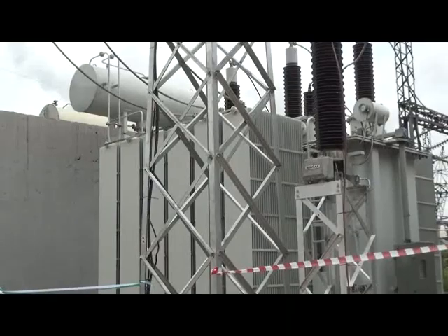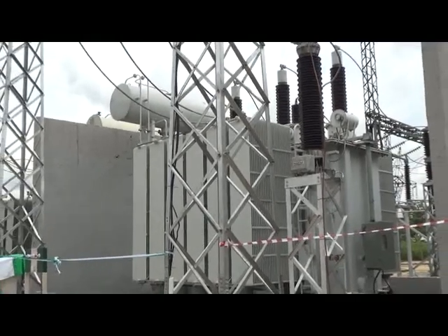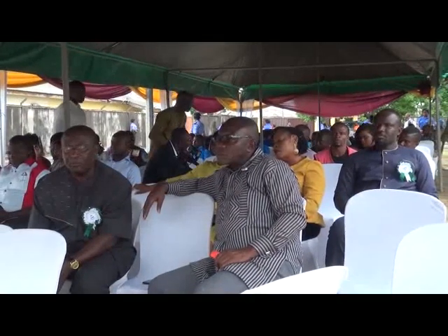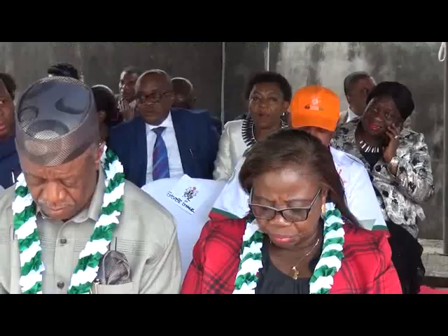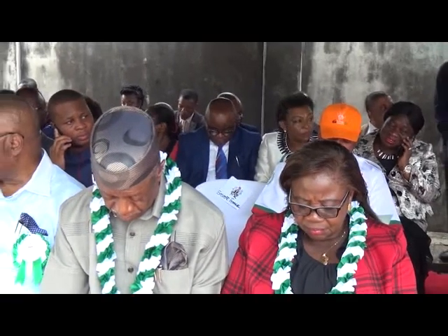It is now being commissioned here today by His Excellency, the Governor of Akwa Ibom State. He said the commissioning of the 60 MVA transformer will improve power supply for PHEDC customers in the state. Communities including Uyo, Oron, Umbo, Ikot Ekpene, Airport, Abak, SCN Udin, Mpat Enin, Unan, and their environs will experience remarkable improvement in power supply. With this development, TCN has not only established adequate transformer capacity to serve these areas but has also provided the necessary redundancy in line with the N-1 reliability criterion at this substation.